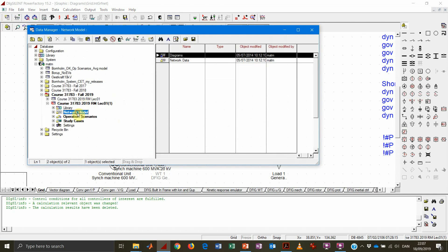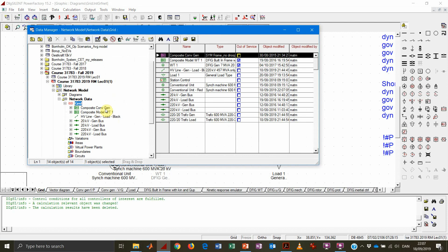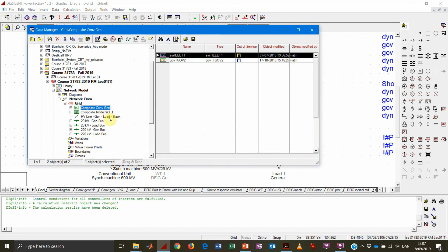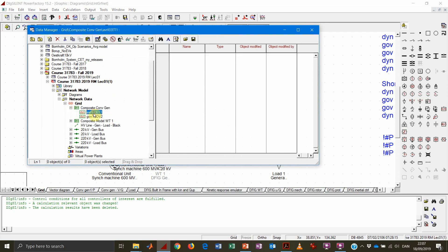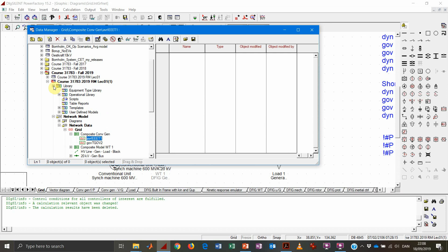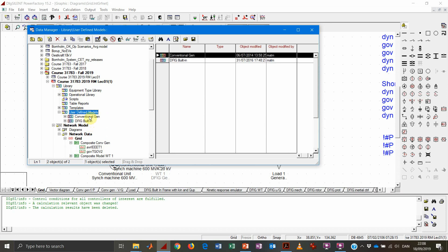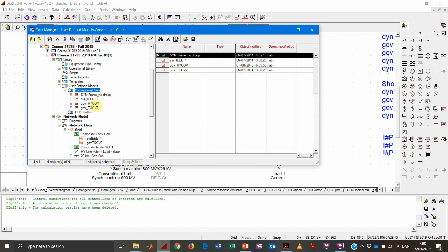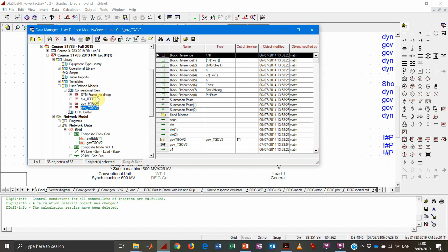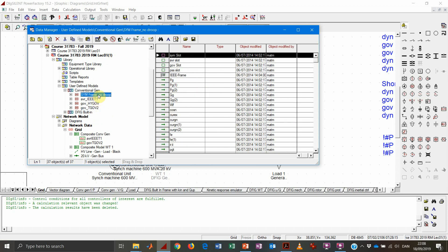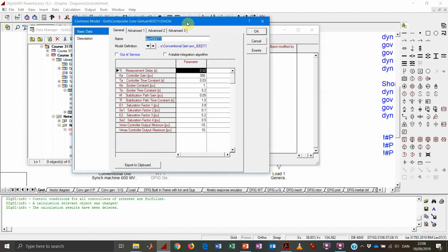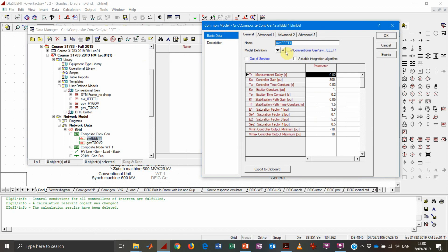What we need to do now is equip the new machine with a new composite model. The composite is located in the grid subfolder, and inside the composite we have the common models. The composite model and common models reference a composite frame and block definitions that specify how the frame should look. If we go into the local library, we can see the model definition for the governor, the model definition for the AVR, and the composite frame definition. Opening the AVR element shows that it points to a model definition.